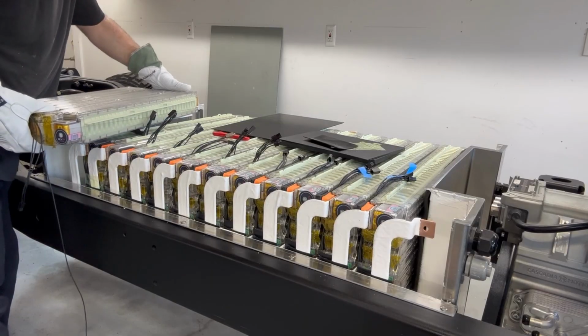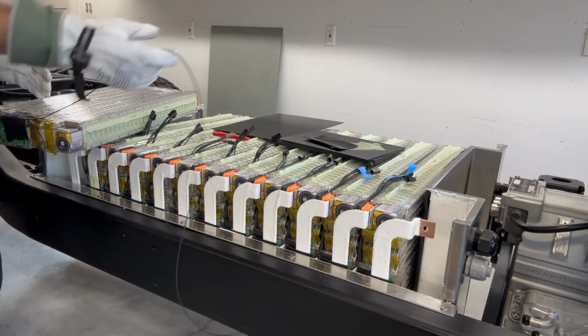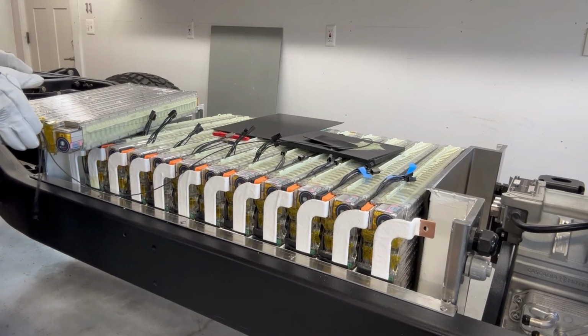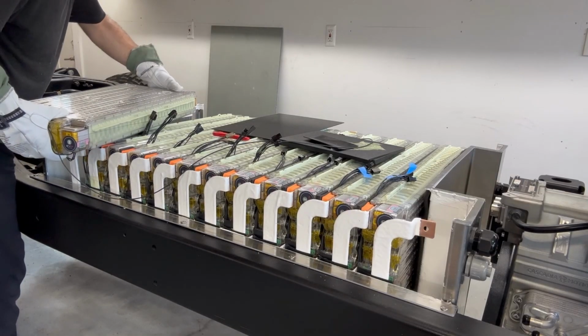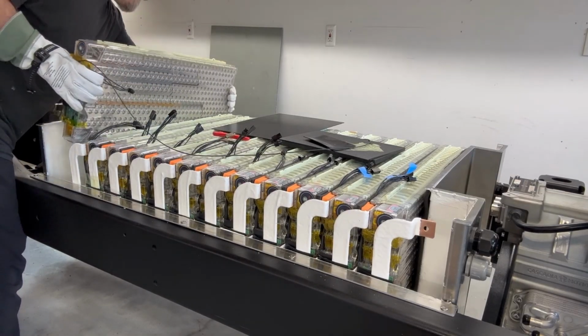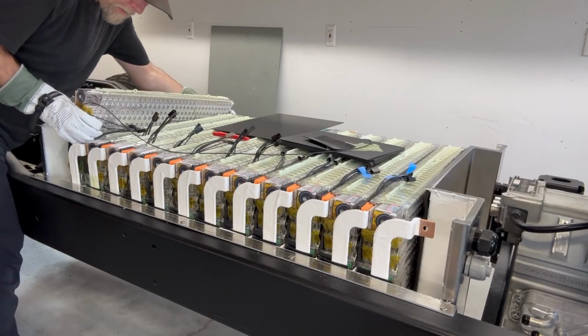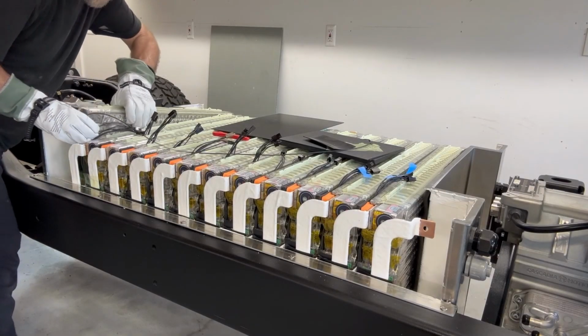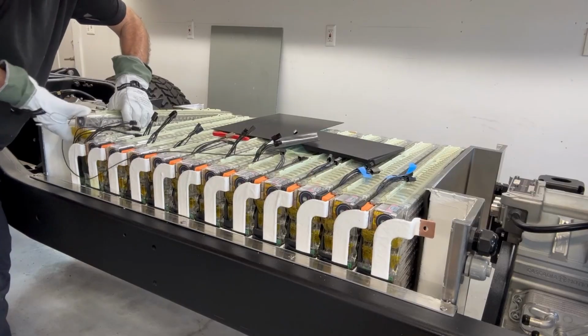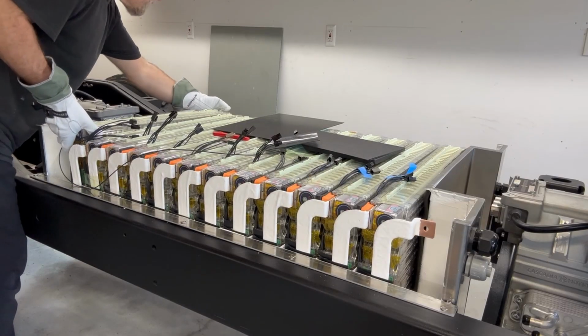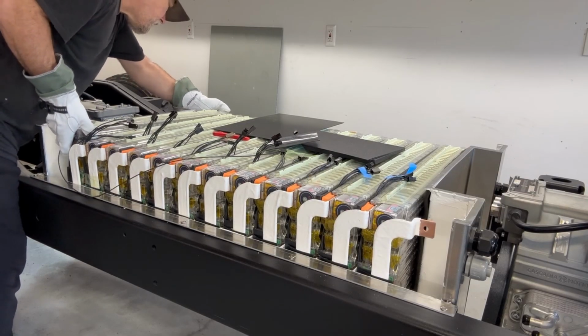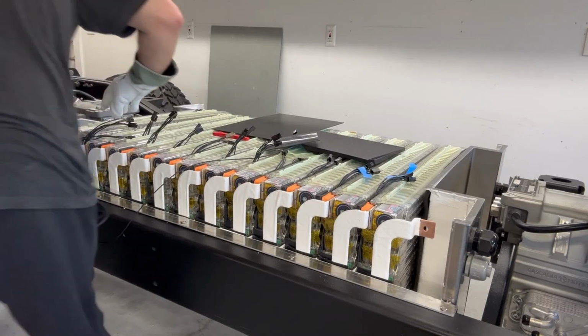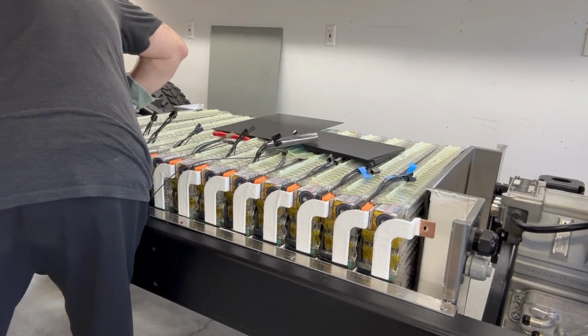The last module has a slightly different low voltage battery board connector. Instead of having two pairs of 3 wires coming from the circuit board, this one has one 3-wire whip that connects to the previous battery and one 1-wire whip with a long extension that runs up to the front of the box. This 1 wire will connect to one of the 4 connections going to the BMS, with the other 3 wires from the BMS going to the first battery in our secondary box.